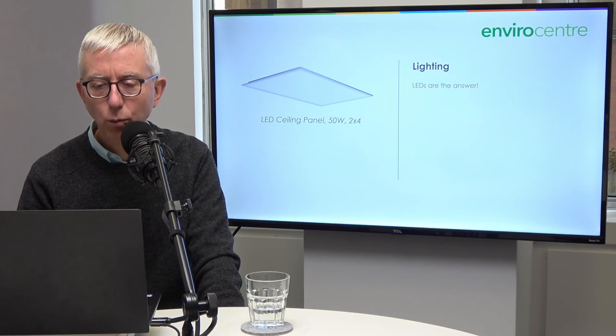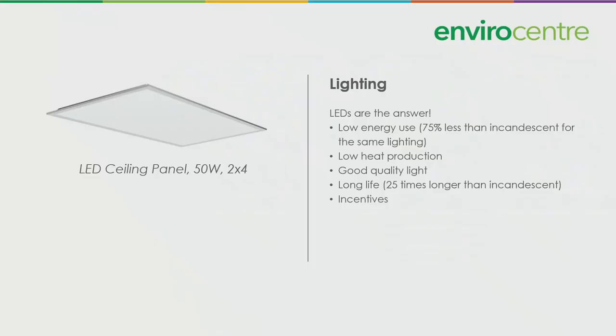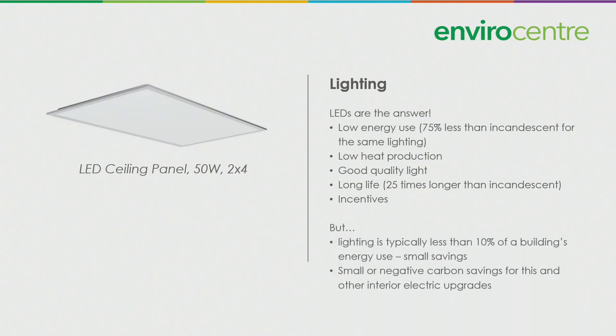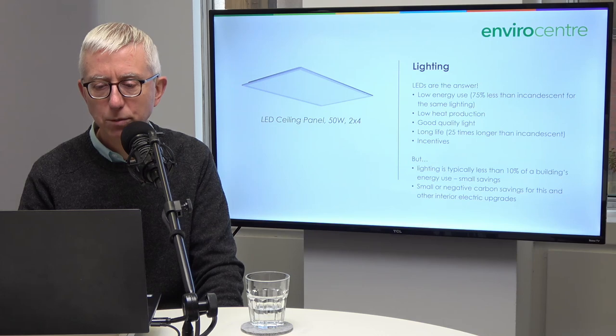Lighting, in the lighting world, LEDs are the answer. Low energy use, good quality light, long life, incentives. But keep in mind that it's typically less than 10% of the building's energy use, so there are small energy savings. And you have small or negative carbon savings for this and other interior electric upgrades because you're shifting the heating load onto your gas systems, perhaps.